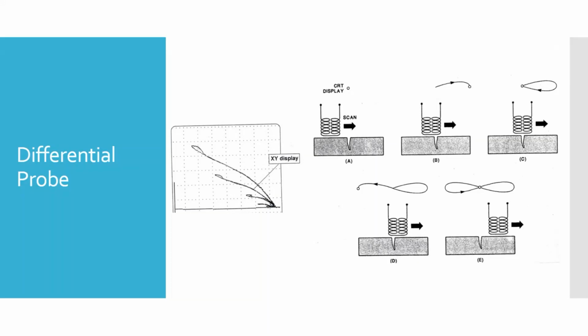As we come back, as both coils start to get over the flaw, they're going to be balanced with each other again, pulling that indication back to the neutral center point. It made a little loop out to the right. Then, as we continue to move, because the coils are wound opposite of each other, the eddy currents cause the indication to go the opposite direction, so it loops out to the left. Then as we get past it and back over a good area of the metal, it returns to its neutral point. That's a real balanced, ideal situation.